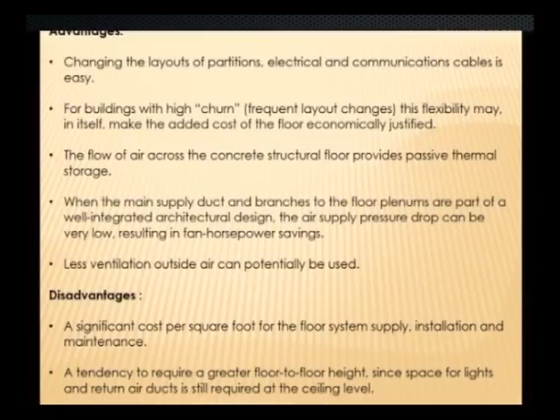The flow of air across the concrete structural floor provides passive thermal storage. When the main supply duct and the branches to the floor plenums are part of a well integrated architectural design, the air supply pressure drop can be very low, resulting in fan horsepower savings, and less ventilation outside air can potentially be used. The disadvantages are a significant cost per square foot for the floor system supply, installation and maintenance, and a tendency to require a greater floor to floor height, since space for lights and return air ducts is still required at the ceiling level. Those are the disadvantages.